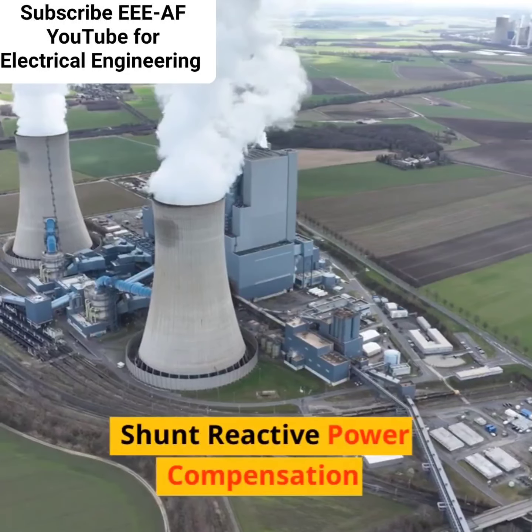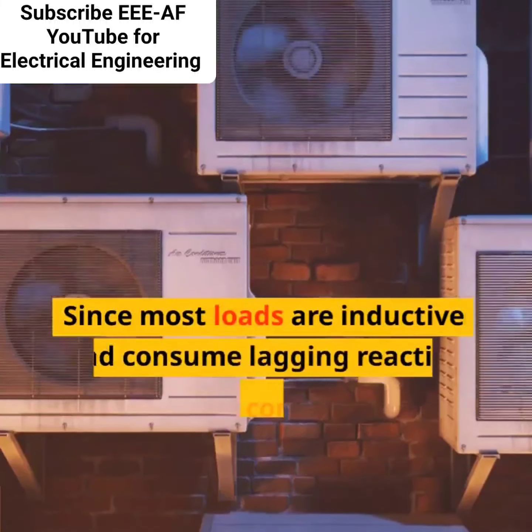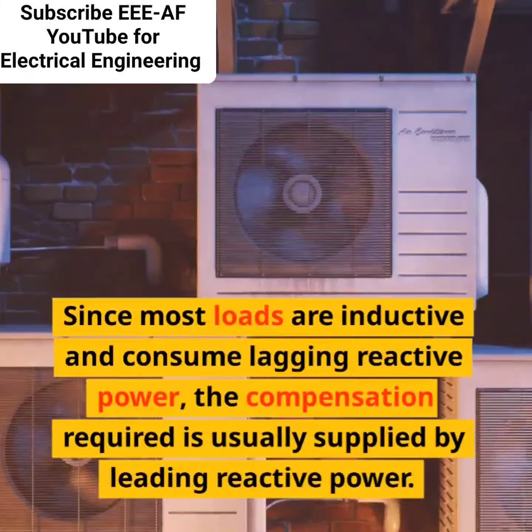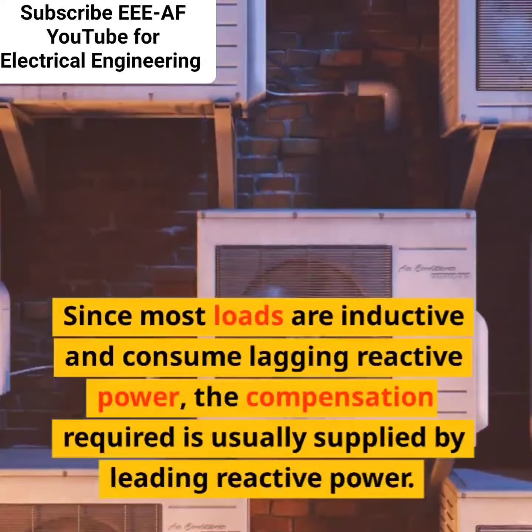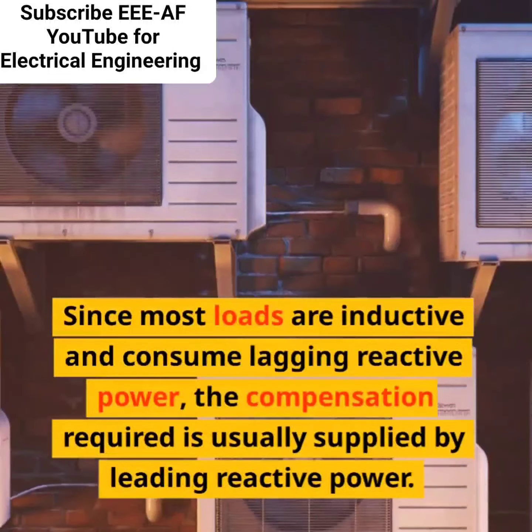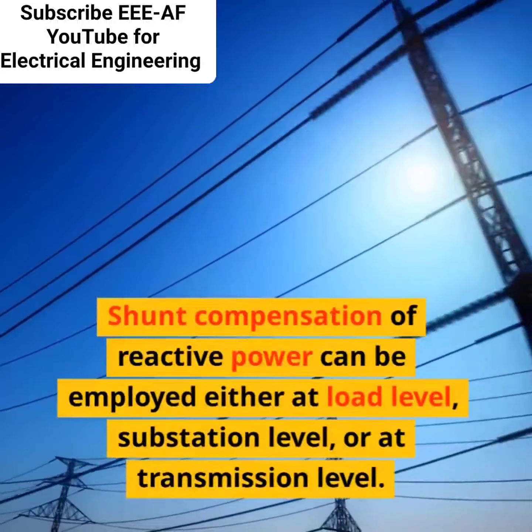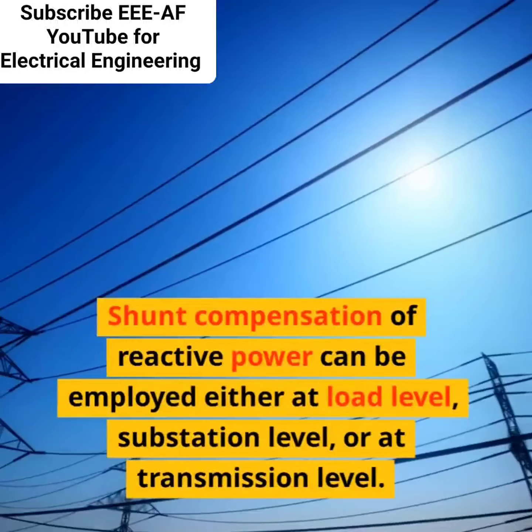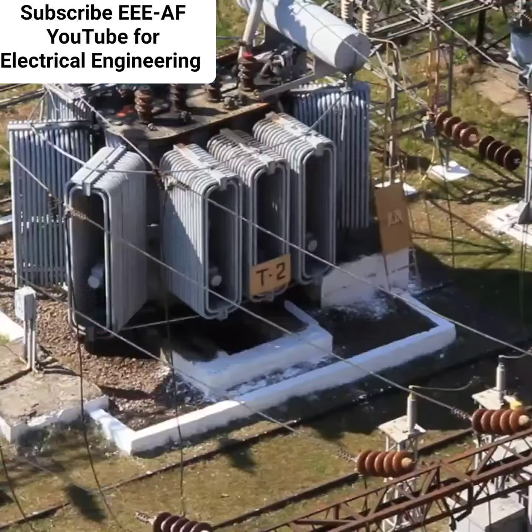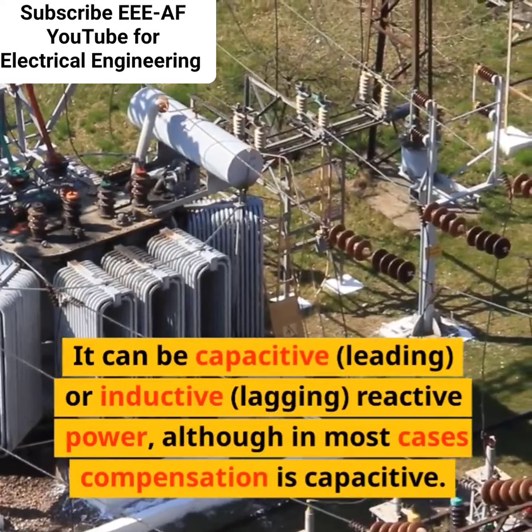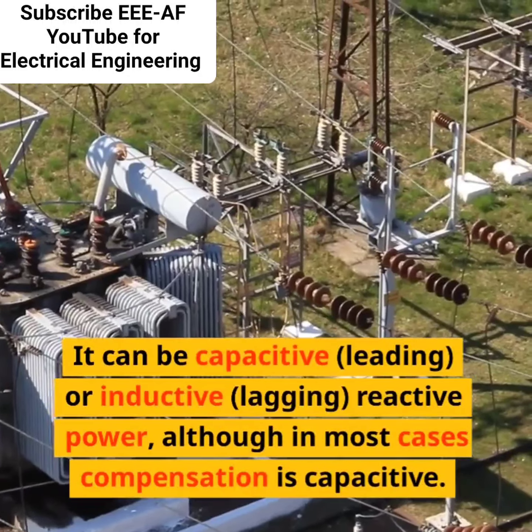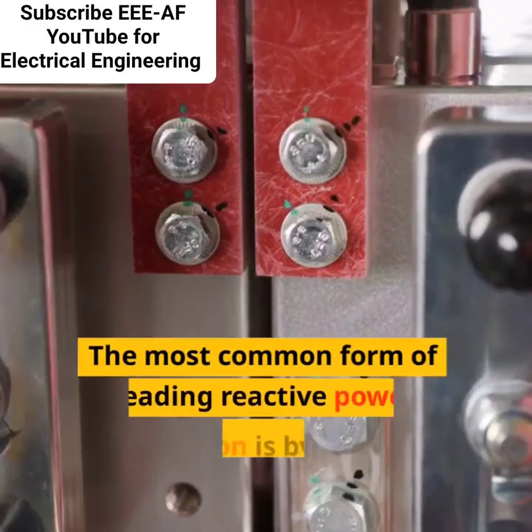Shunt reactive power compensation. Since most loads are inductive and consume lagging reactive power, the compensation required is usually supplied by leading reactive power. Shunt compensation of reactive power can be employed either at load level, substation level, or at transmission level. It can be capacitive, leading, or inductive, lagging, reactive power, although in most cases compensation is capacitive. The most common form of leading reactive power compensation is by connecting shunt capacitors to the line.